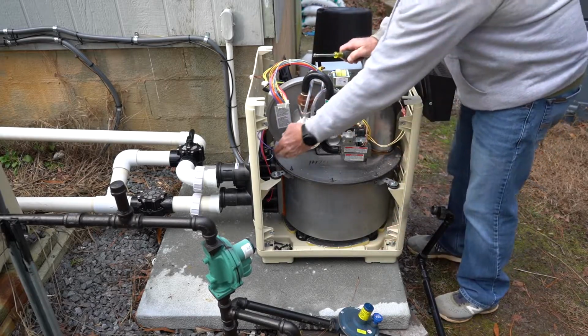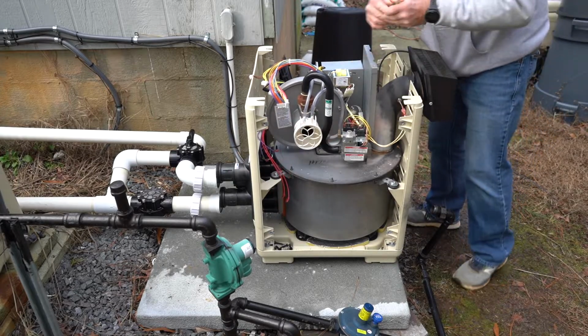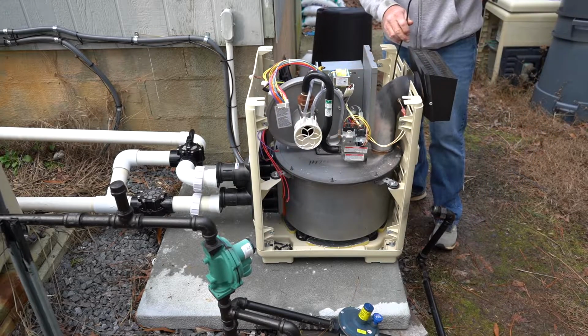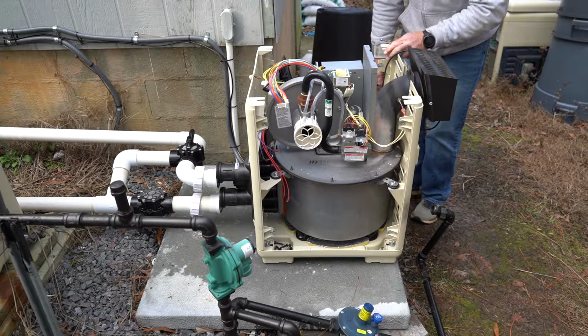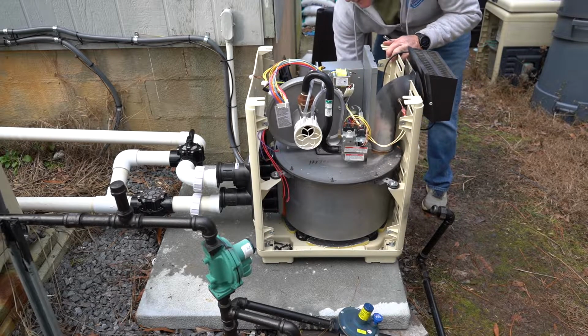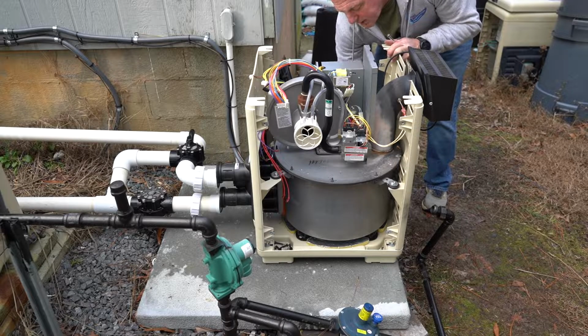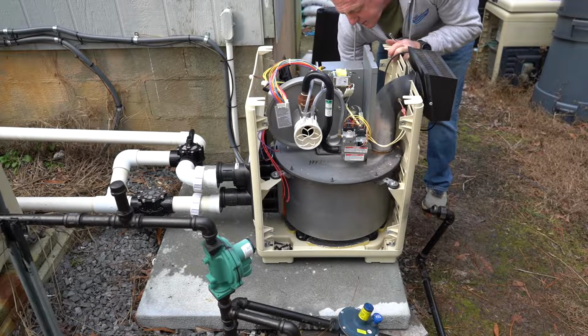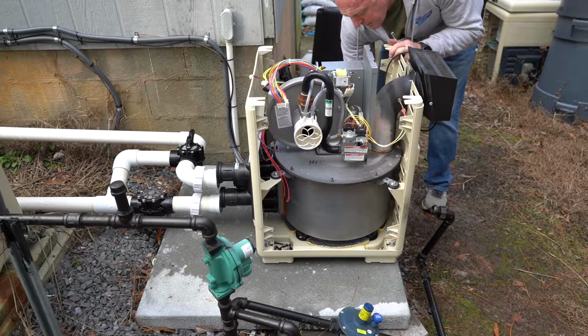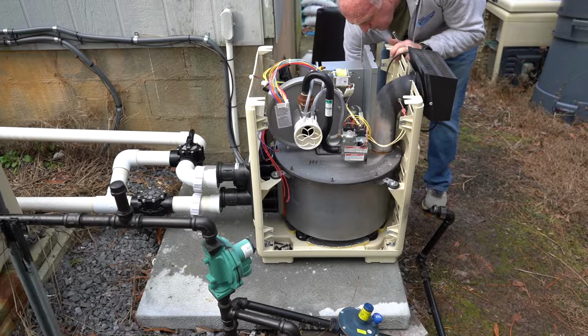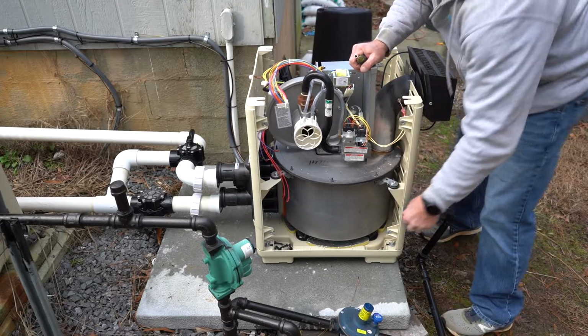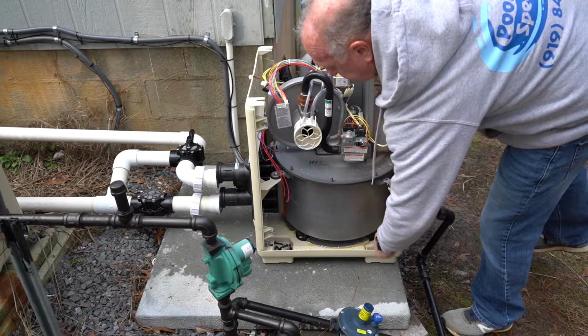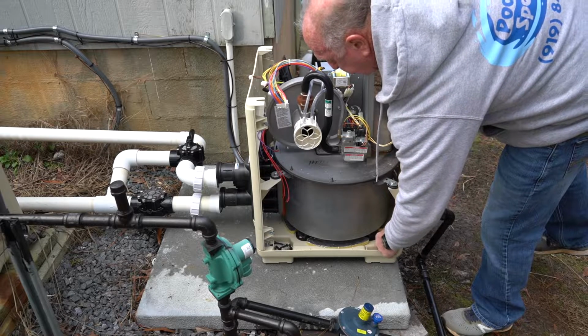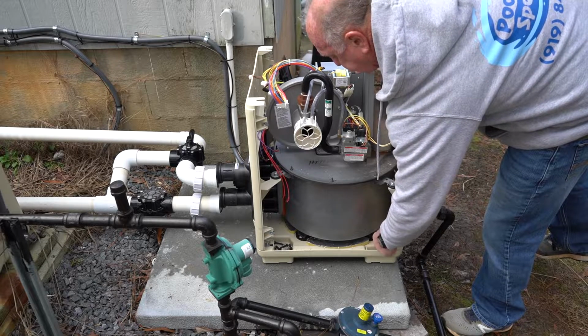You can see that all my wires to all my sensors have been removed on both sides. I even removed the automation wire. Now, this is kind of tight, so just as there's wing nuts on top, there's wing nuts on the bottom as well. My recommendation is go ahead and remove those wing nuts on the bottom. This way, this panel is free to move however you need it to move in order to get this out.